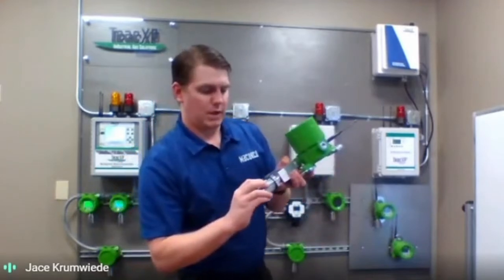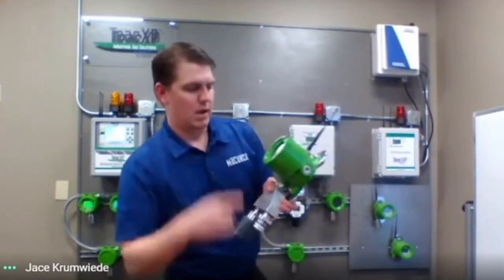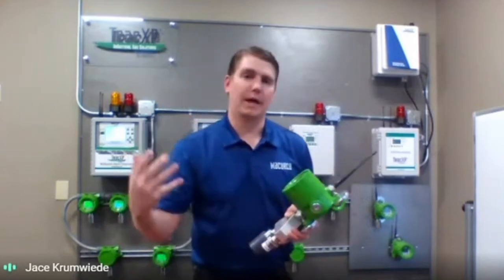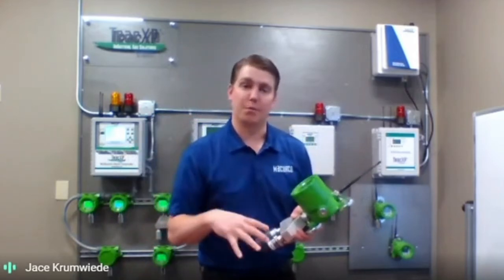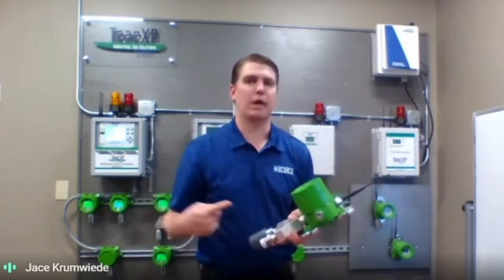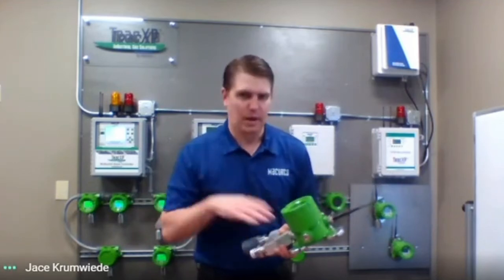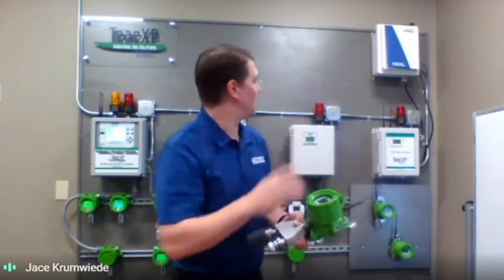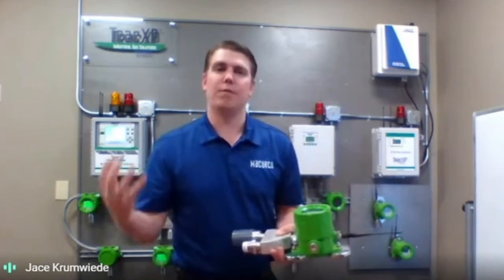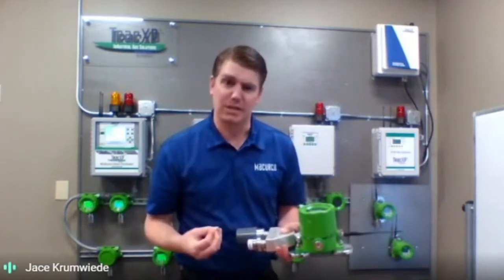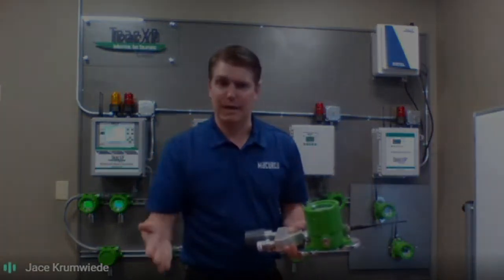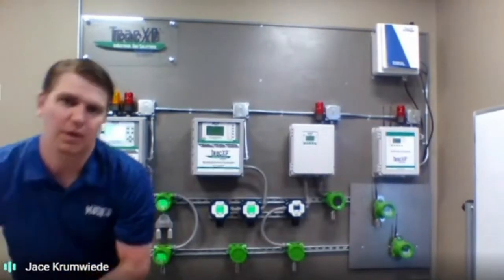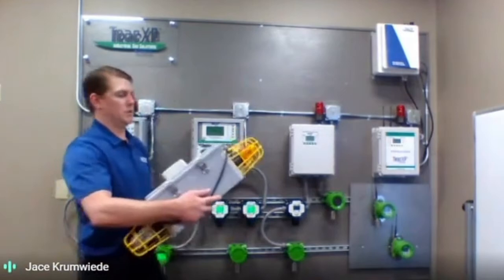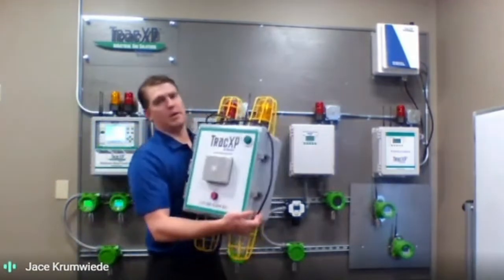pop it in there, get your sensor housing cover on, and if you turn it on, it's going to ask you if you want to upload that information into your transmitter. Very quick and easy process. You'll have it in there. It syncs up with the controller. So it makes it very easy if you need to change sensors. There are also various horns and strobes, notification appliances that we offer in conjunction with our control panels and our gas detectors.